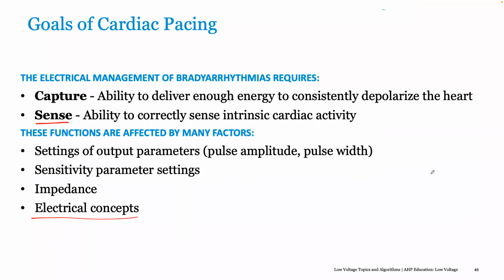So I was going to say for Medtronic, obviously Medtronic has got an adaptive, the auto capture management and auto sensing that it's called adaptive management. The other thing to bear in mind, if say for instance you're having a higher threshold since after implant, and you want to put adaptive on because it might keep creeping up. I know that with Boston, if you do put that capture management on, it does have a limit of V output, so it won't go any higher than 5 volts. So you could run into trouble with that.